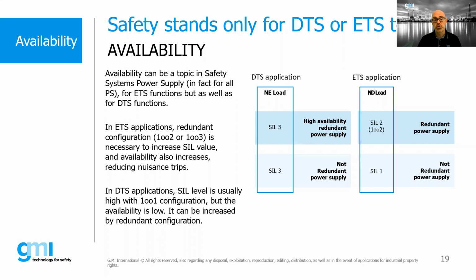As regards energized to safe applications, typically normally de-energized loads, as mentioned above, redundancy is essential to reach a SIL2 or SIL3 level. In fact, without redundancy, with a single safety power supply, only the SIL1 level can be reached, and also availability to the process is low. But by composing a configuration 1 out of 2 or 1 out of 3, it's possible to get a higher SIL level, up to SIL3, and at the same time increase the availability of the process also for energized to safe applications.